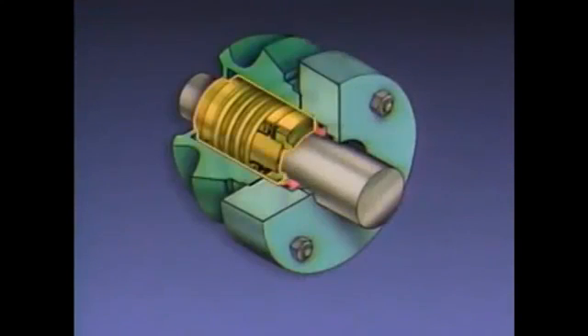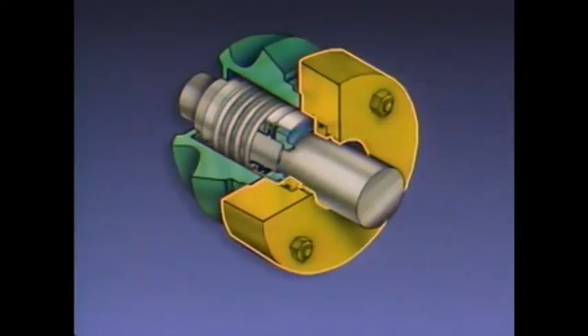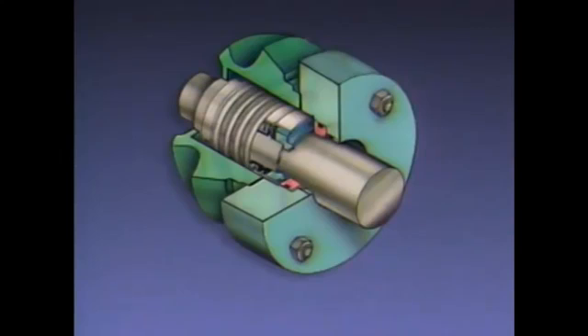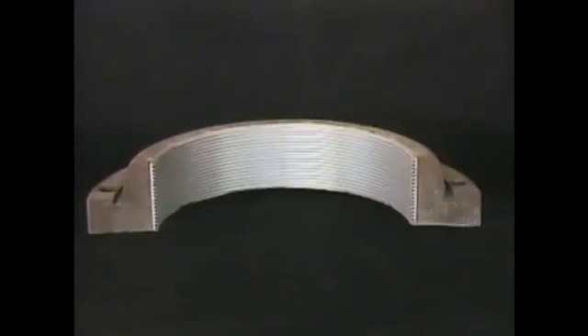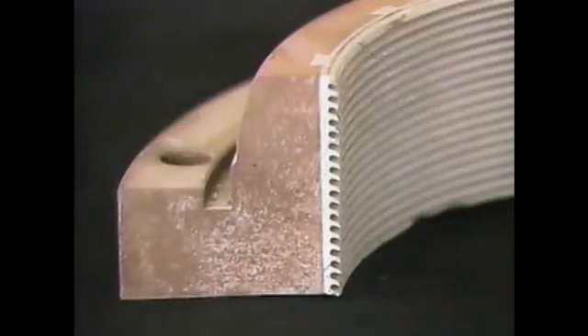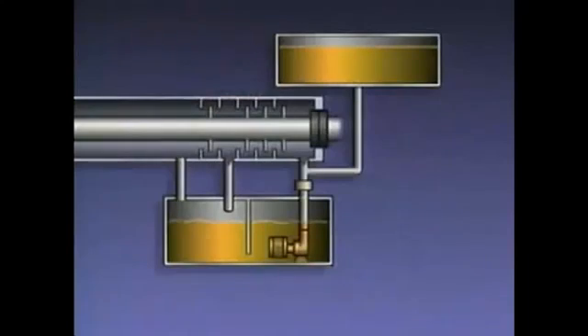The next components we'll look at are seals. Several types of seals can be used to prevent leakage inside a compressor and out of a compressor. A mechanical seal consists of a rotating element and a stationary element that can be used to form a seal between a rotating shaft and a stationary housing. A labyrinth seal consists of a series of ridges that create an intricate path that makes it difficult for leakage to get through the seal. Both mechanical seals and labyrinth seals may be used with a seal oil system.